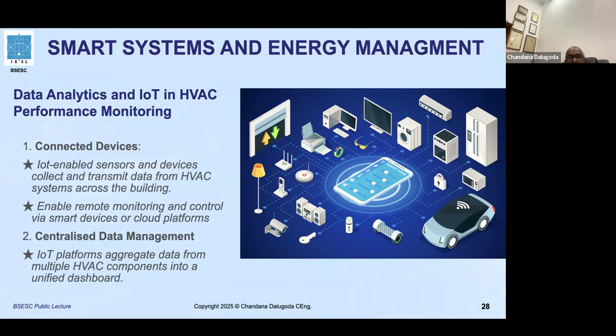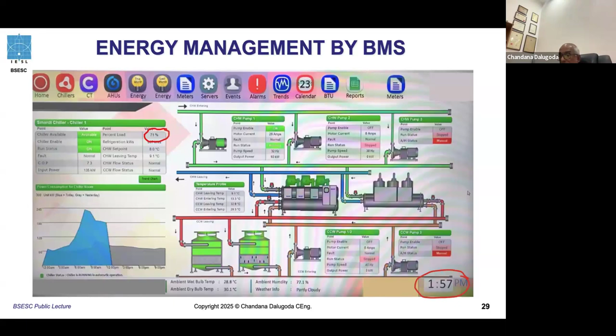And the BMS. Quite unfortunately, BMS in Sri Lanka is just merely a showpiece. They look at the monitor, your chiller is working, the fans are rotating, the pumps are rotating, all on-off and monitoring purposes. No, what we are talking about, energy saving strategies, has to be used with a BMS. Now this BMS output, I took this on a weekday, almost 2 p.m. Now you will see the chiller loading is only 71% at 2 p.m., the peak, thanks to BMS operation with various energy saving strategies. I'm going to discuss these things quickly.